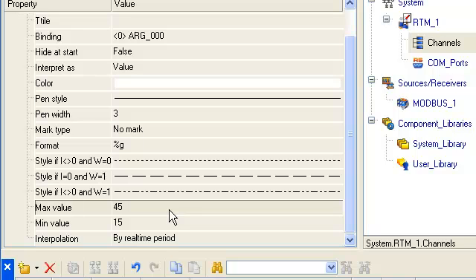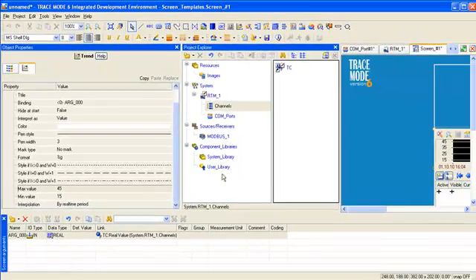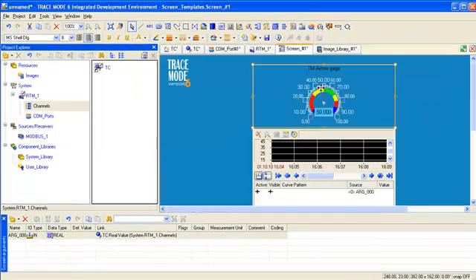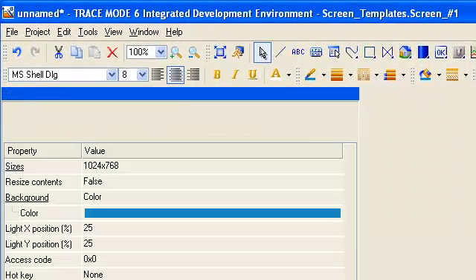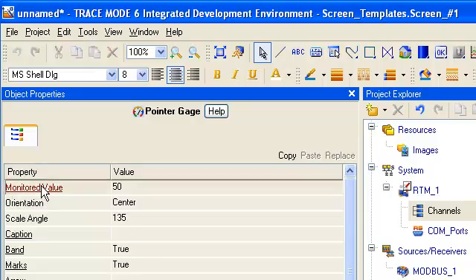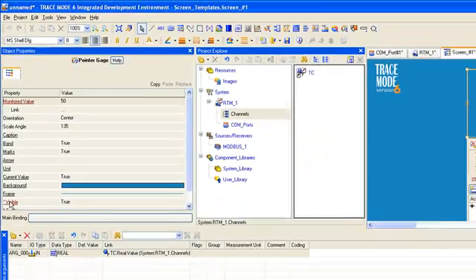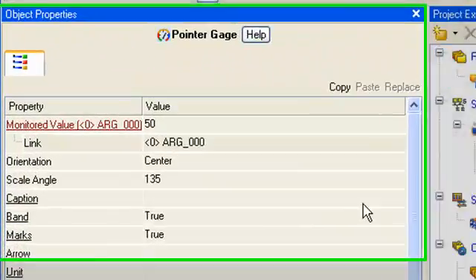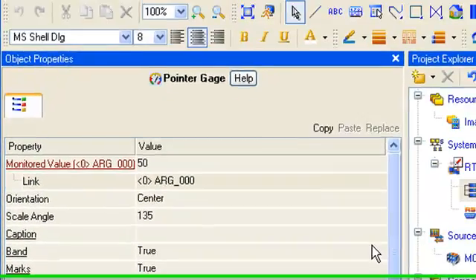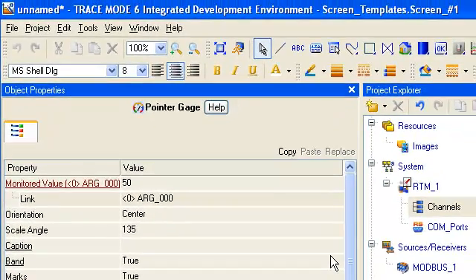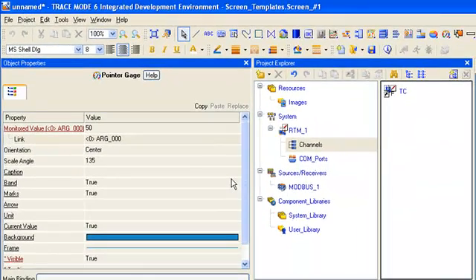In order to visualize the room temperature on graphic element gauge, we highlight it with the left mouse button and open internal attributes. For internal attribute monitored value, we make link to our argument with the help drag and drop. The scale is kept unchanged by default.